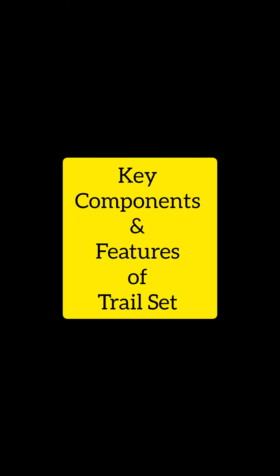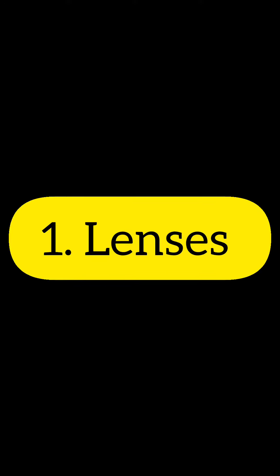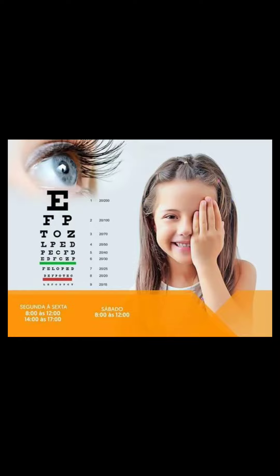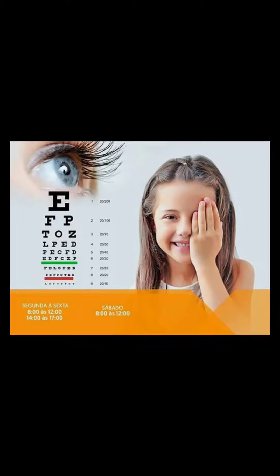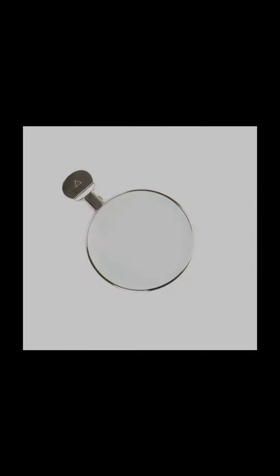Here are some key components and features of the trial set. Number one, the set includes a variety of lenses with different powers and types. Spherical lenses are used to correct myopia, hypermetropia, and presbyopia. Cylindrical lenses are used to correct astigmatism. Prism lenses are used for diagnosing and treating binocular vision disorders. Accessories such as occluder, pinhole, and Maddox rod are included for specific tests.